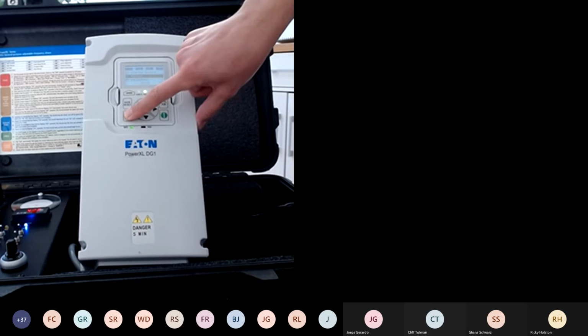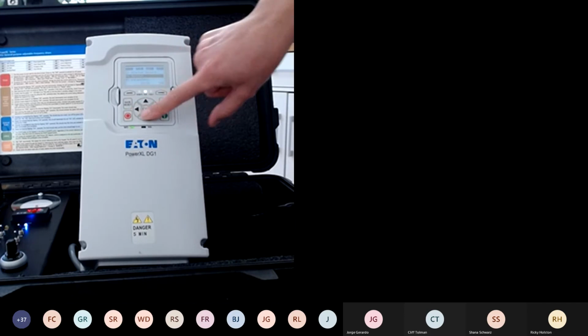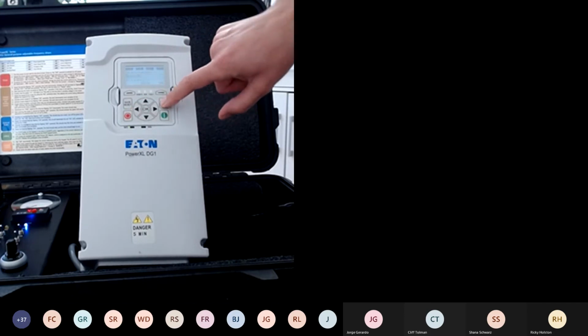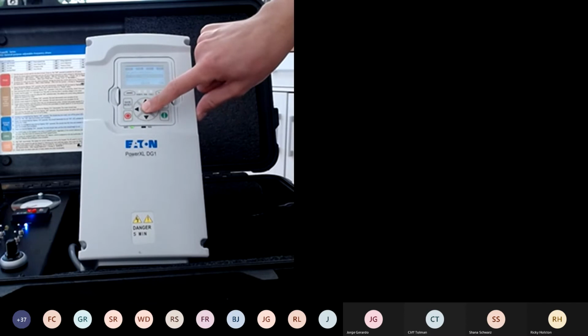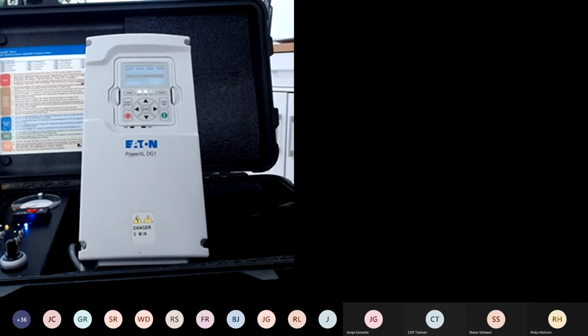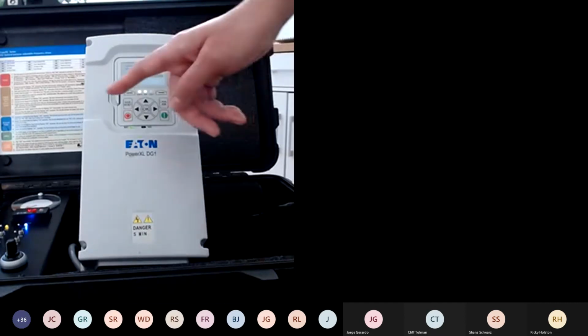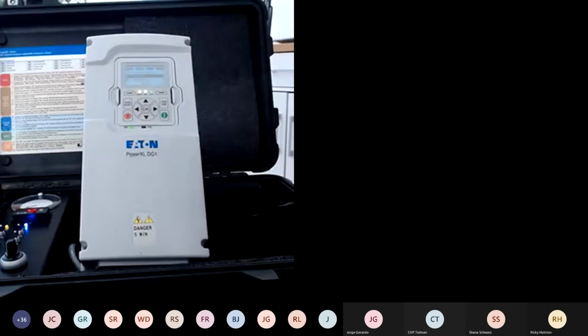So to make any changes, let's stop the machine. Go back to remote control. And now you see that the IOs, if you have the screen here oversized, you can control through DI1 and then use the analog potentiometers, and that could be a 0 to 10 volt signal, 4 to 20 milliamp signal, controlling the speed of your pump.